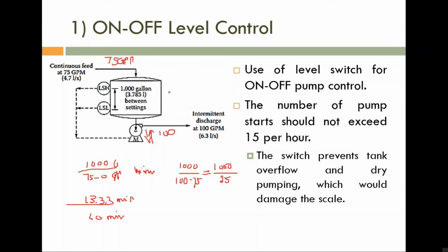Is it okay? So for one cycle, meaning one filling and one emptying, the time required is 13.33 plus 40, which is 53.33 minutes. Is it okay? So this is the time required for one cycle. You can see that per hour the number of starts of this pump is 1, or rarely 2. Am I correct? Because this is one cycle of that pump.